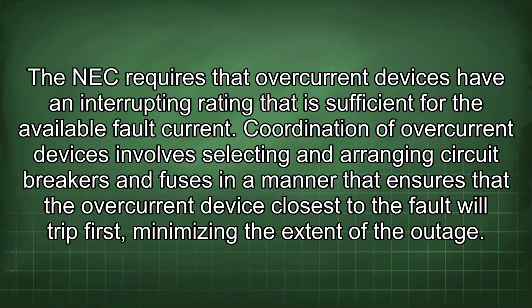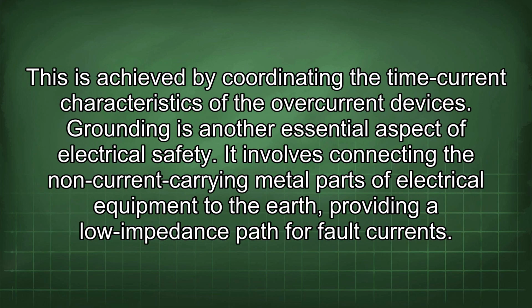Coordination of overcurrent devices involves selecting and arranging circuit breakers and fuses in a manner that ensures that the overcurrent device closest to the fault will trip first, minimizing the extent of the outage. This is achieved by coordinating the time current characteristics of the overcurrent devices. Grounding is another essential aspect of electrical safety.